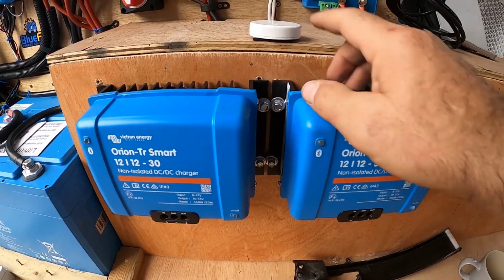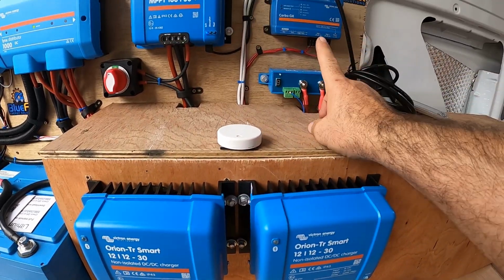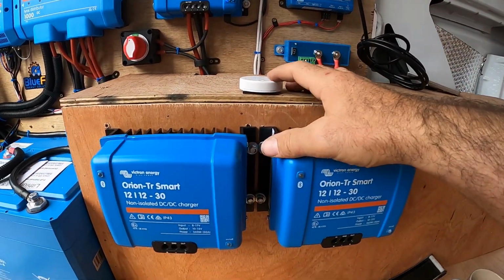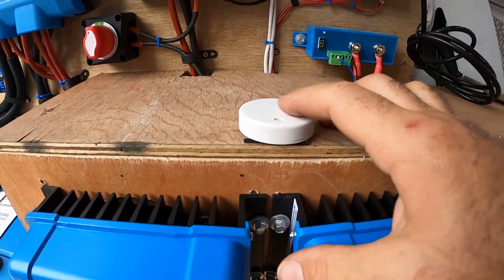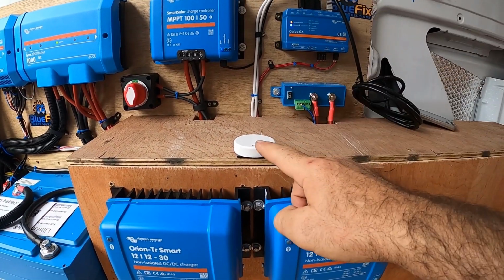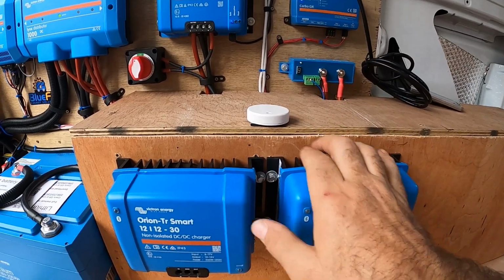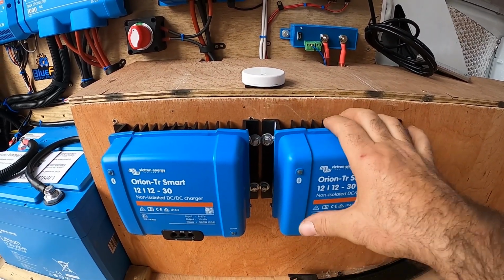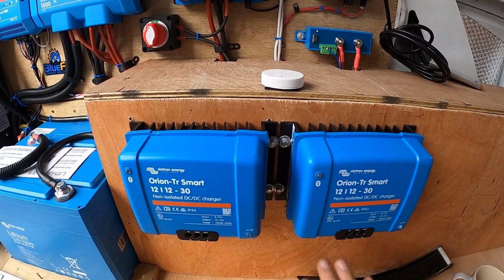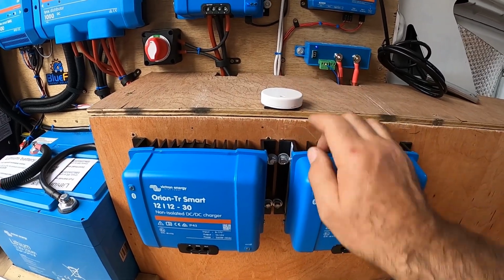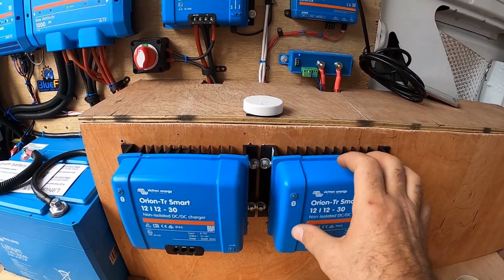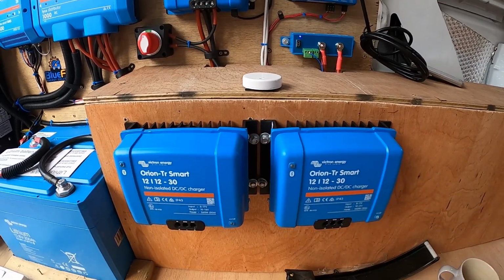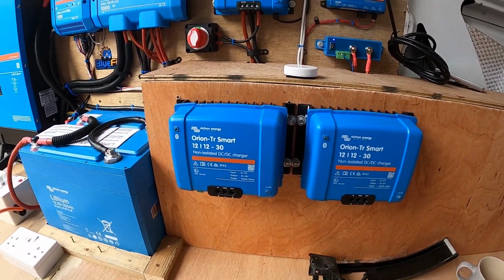These fans are operated and controlled by the Cerbo's relay, and the Ruuvi smart sensor here tells the Cerbo at what temperature to open up the relay and turn these fans on. We've got them set to come on at 20 degrees and go off at 19, so if it's ever more than 20 degrees here, both fans will be cooling the back of these Orions, making them much more efficient.